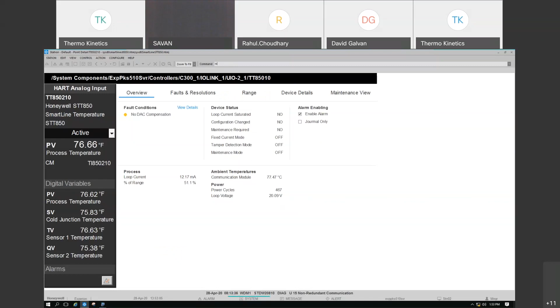So before I close this out, I want to show you one more thing over here on the PLC. As you can see here, this PLC looks identical to this device here, which is the UOC, the Unit Operations Controller. Same part numbers, same modules, same everything. If, for instance, I want to use this PLC and make it a DCS, a supervisory system, I can flash this CPM, Central Processor Module, and make it a C300. I can make it a supervisory DCS with the UOC, and you can tie that into your network as well, to your FTE. So it's the same part number, same hardware, just a different intelligence, a different personality that we load onto the card itself. Okay, just wanted to make you aware of that piece.